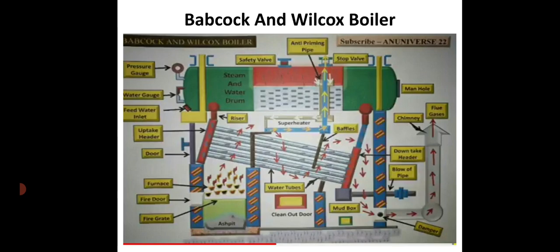This boiler consists of a steam water drum mounted on fire brickwork. Hot gases from the furnace follow a zigzag path through the fire brick baffle before going to the chimney through the damper. The damper controls the rate of burning and thereby the steam generation. The damper is operated by a chain passing through a set of pulleys.